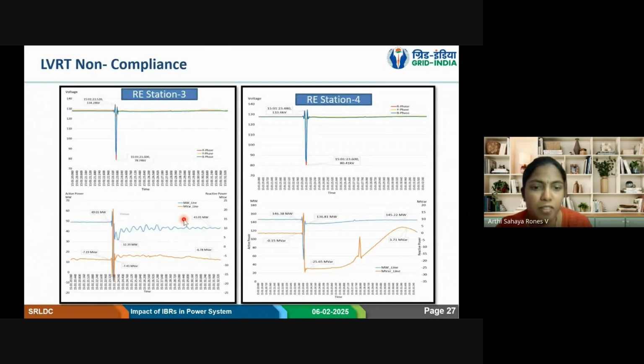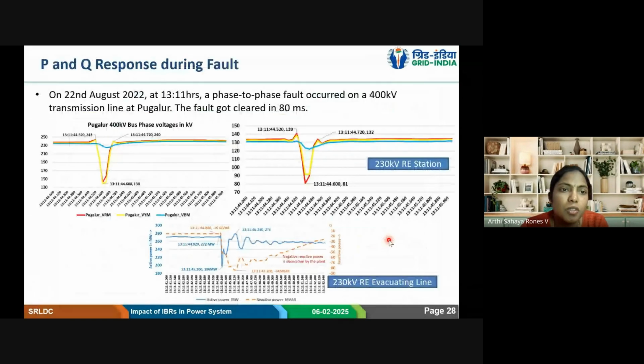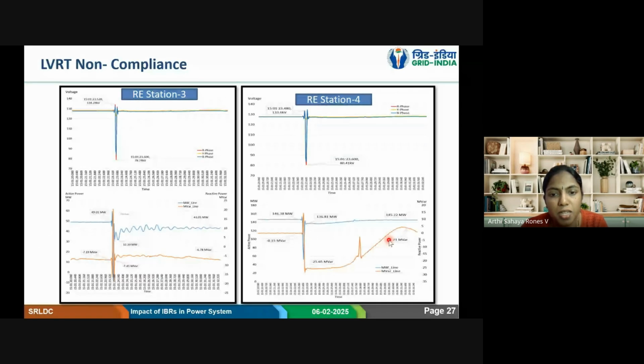For that also, inverters have many protections. When a few protections operate, the inverters will auto turn on. When a few other protections operate, the inverters will require manual switch on. That depends on the type of impact of the grid fault. Some will require manual turning on of inverters. In that case, the grid compliance of 1 second recovery will not be met. So this is station 4. Here it is coming back, but the time taken, the ramping requirement, was not met. So that is regarding the LVRT non-compliance cases.